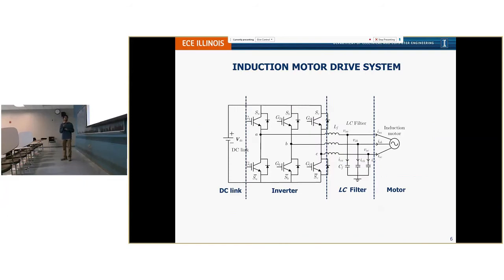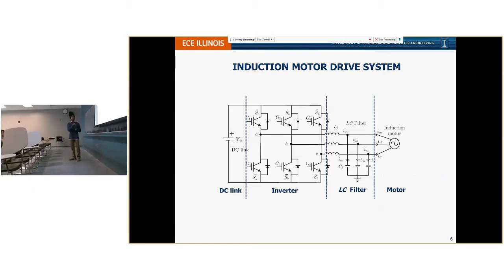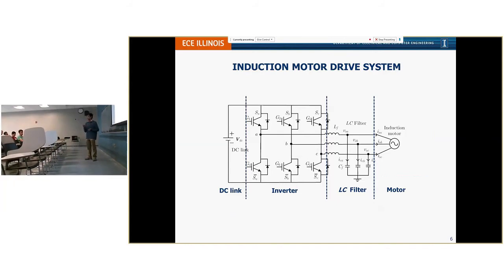When we consider the induction motor drive as a total system, we have the DC link we discussed earlier, the inverter—shown here is a conventional two-level inverter operation, which is predominantly used—and then we also have the optional LC filters.